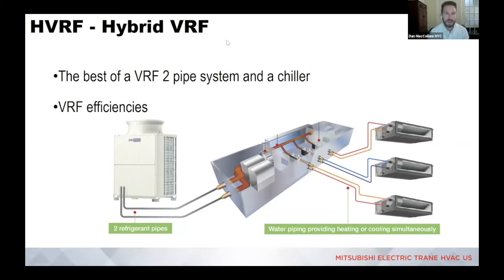So simply put, this hybrid system is what you would be familiar with on the heat recovery side of VRF as it stands today, with a big change at the BC controller. So no longer does that BC controller simply accomplish heat recovery and act as the refrigerant flow traffic cop for the system. What it does now is it has integral heat exchangers that transfer that energy from the refrigerant circuit into a hydronic loop that connects to hot water, chilled water fan coil units. So simply put, those two refrigerant pipes that you see connecting from the outdoor unit to the BC controller are the only refrigerant pipes in this hybrid VRF system. Everything from the BC controller out is all water piping.